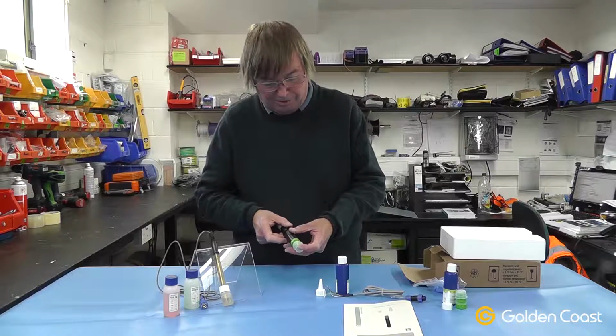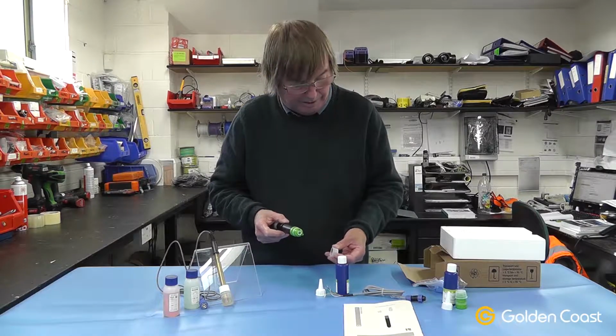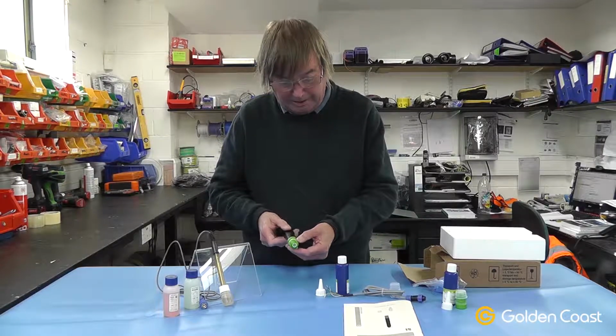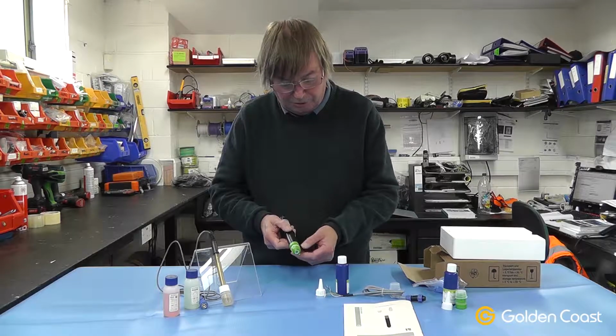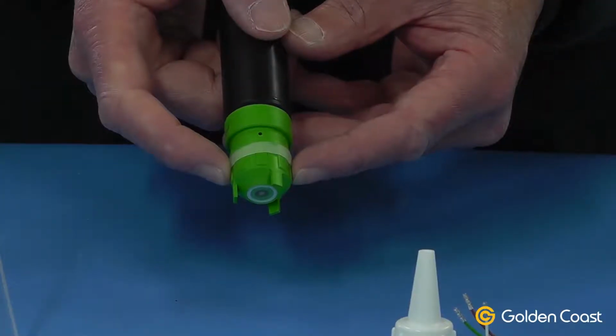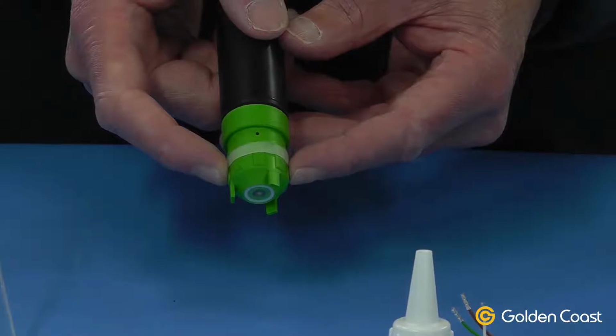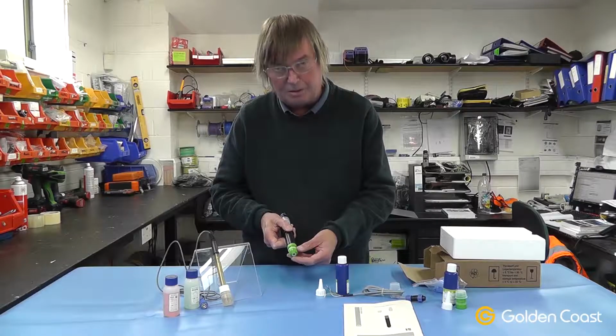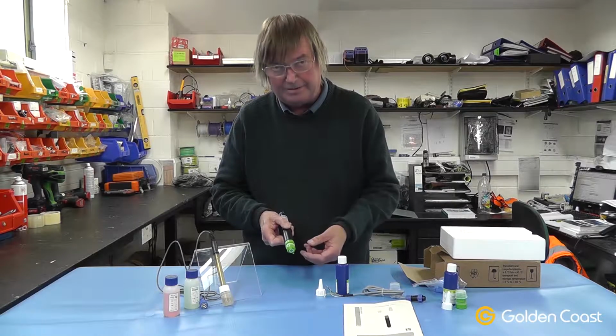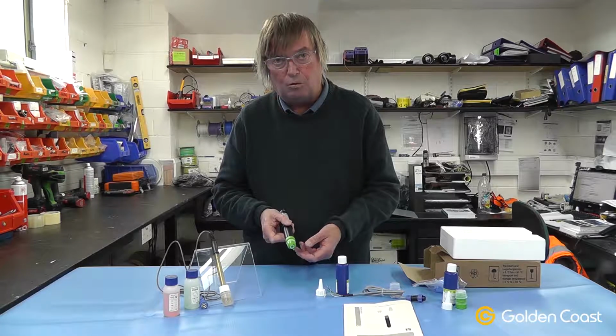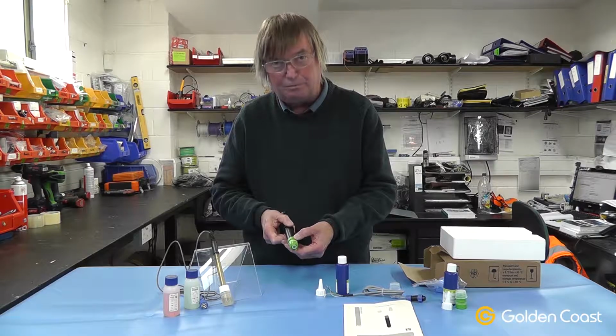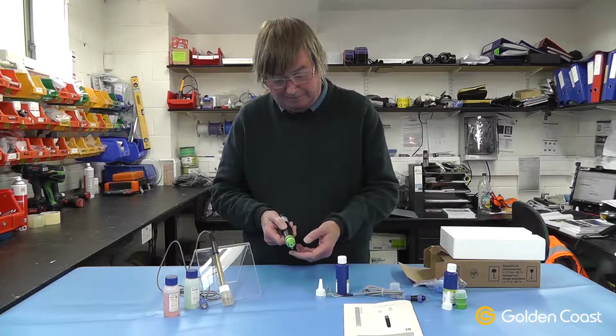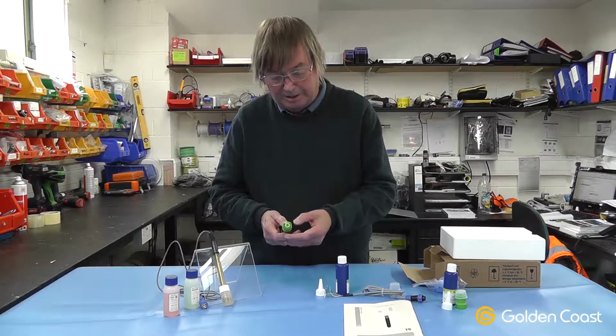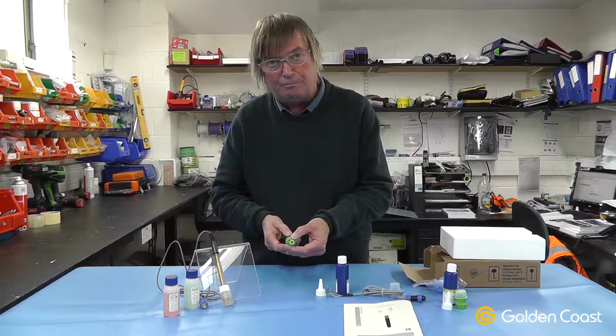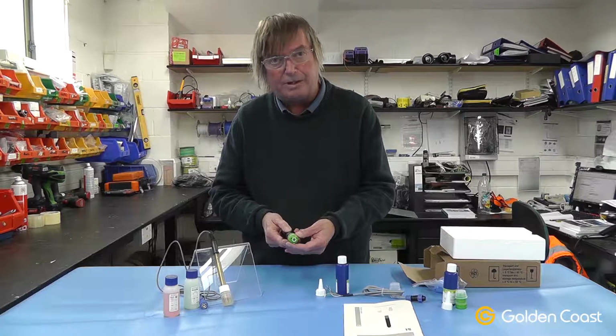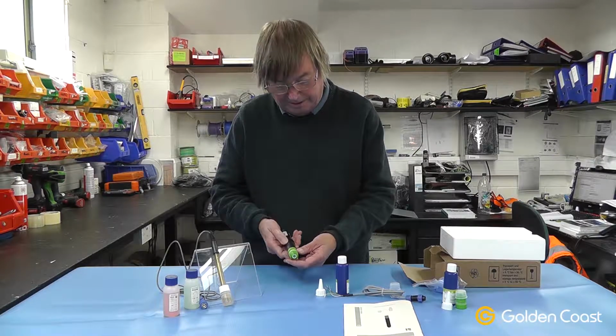The amperometric probe itself comes with a protective cap on the end and a silicone band around the outside, which you can see we've already pulled down, and it exposes a little weep hole in the side of the cap. This must be exposed before you do anything with the cap, either taking it on or off. This relieves the pressure inside the end cap, and if you don't have that hole exposed, you'll blow a hole in the little membrane at the end, and that's damaged forever then.